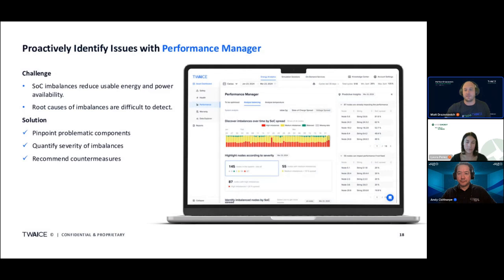Laura also alluded to some of the stuff we found with Performance Manager. Even though the system they operated is more modular, we're still able to detect issues around voltage imbalance and SOC imbalance even at the module level, and we were able to remedy a few of those issues early on from the Performance Manager testing, analysis, and commissioning report testing.